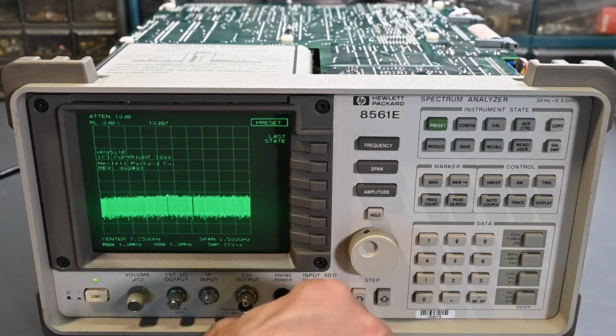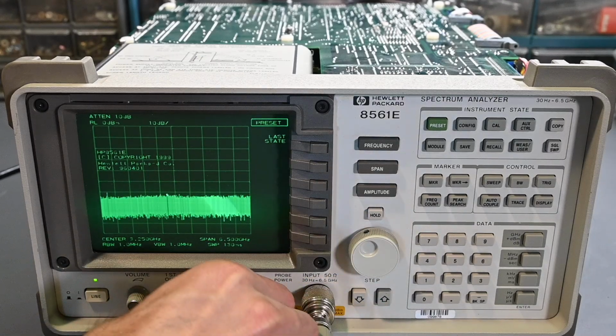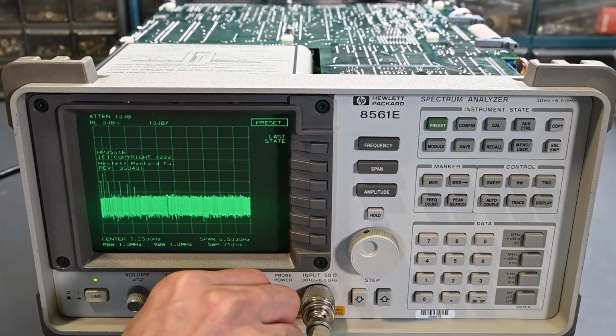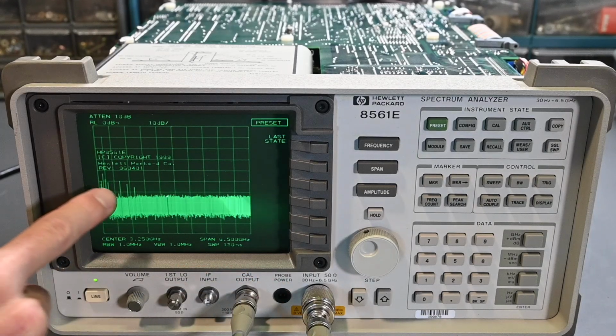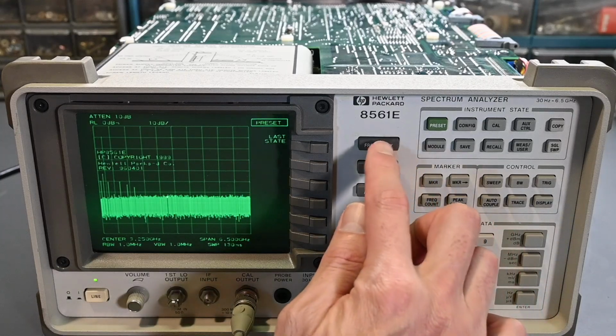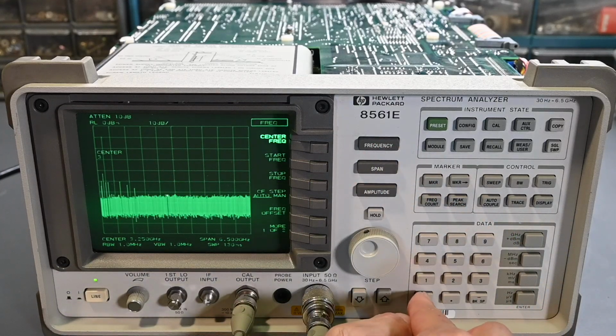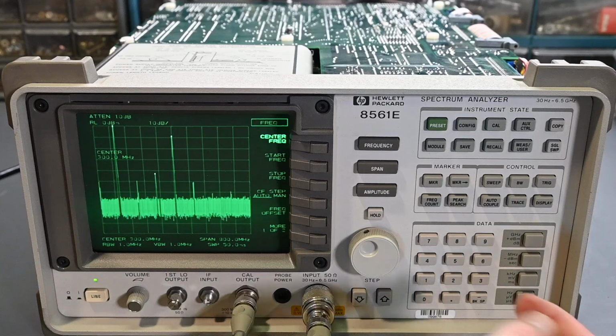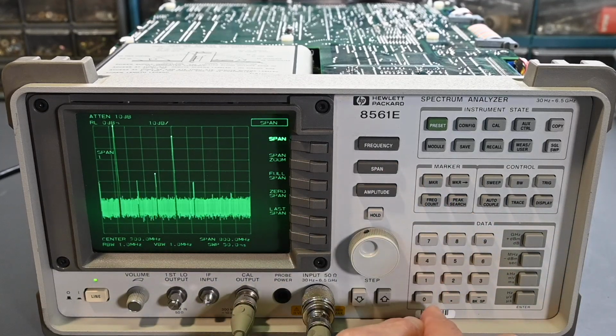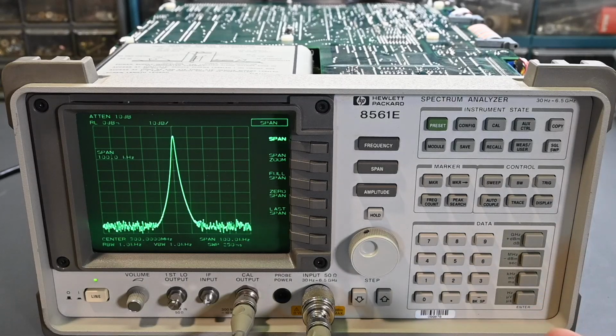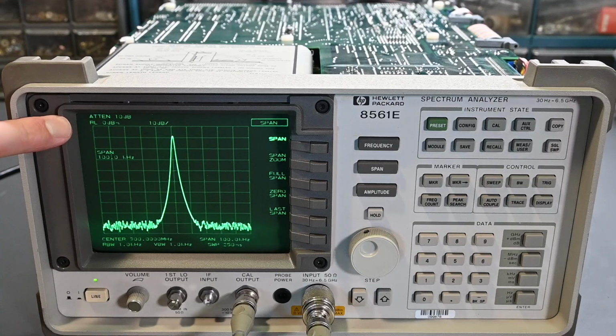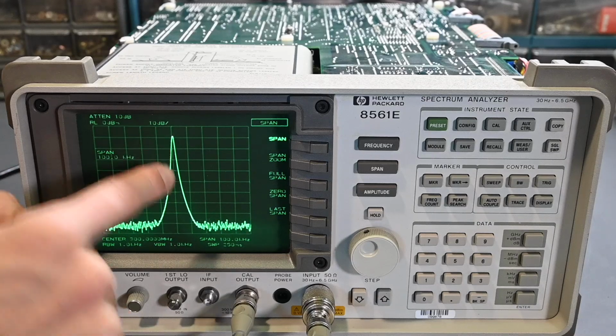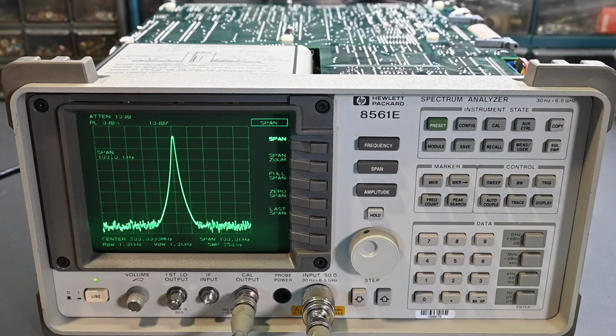So, like that, and let's get this connected over here. Yep. So you can see some signals over here and some harmonics. So let's put 300 megahertz in the center. So frequency, center frequency will be 300 megahertz. And let's make the span, let's say 100 kilohertz. Okay, perfect. So there's our 300 megahertz signal. Now the reference level at the top, so the top graticule, is 0 dBm. And we can see it's down 1 graticule, so that's perfect because that would be minus 10 dBm. That looks very good, so excellent.